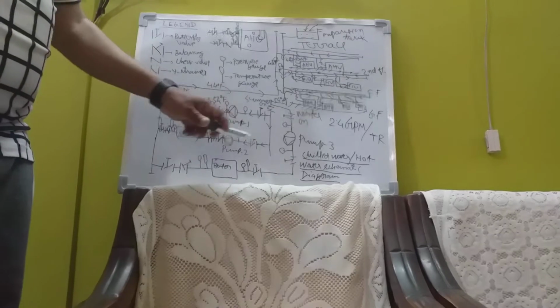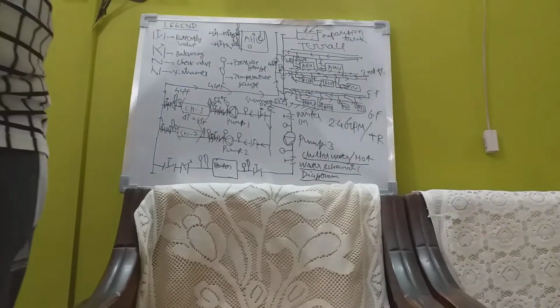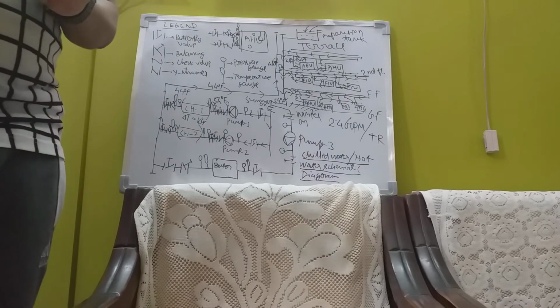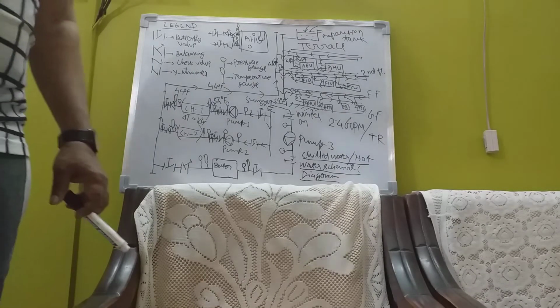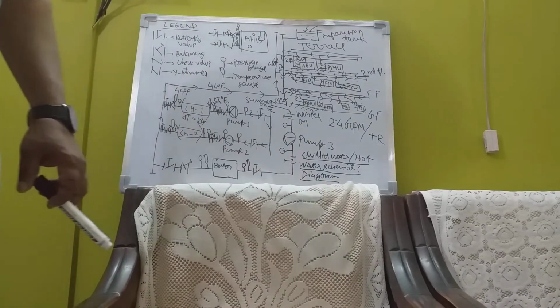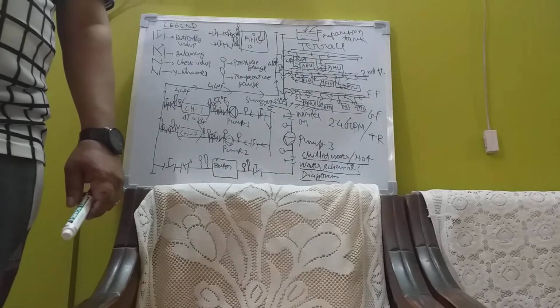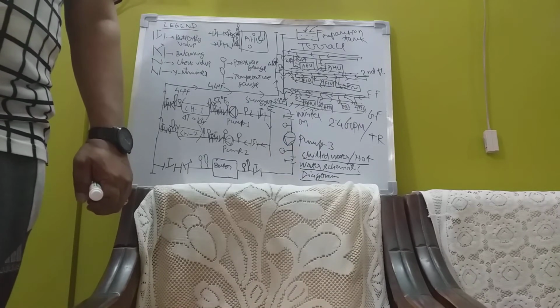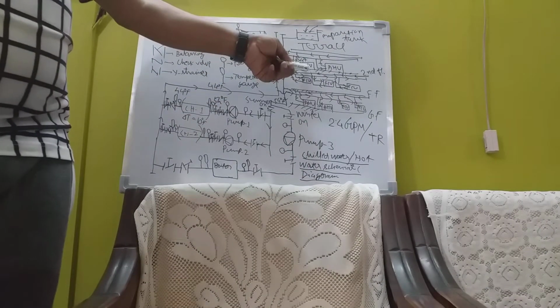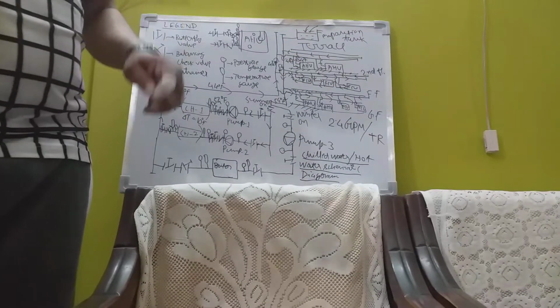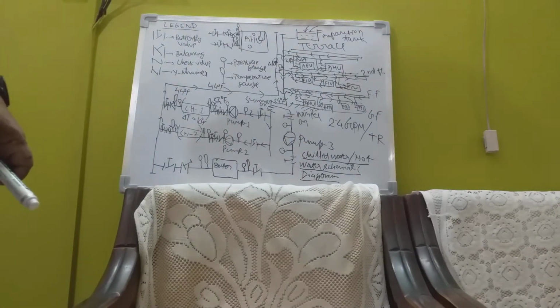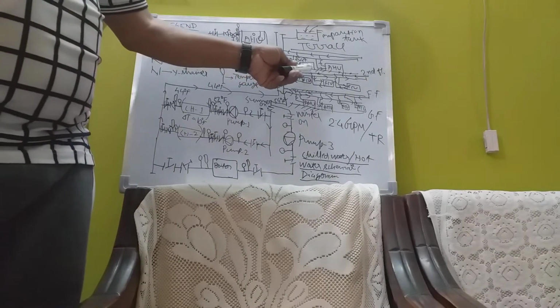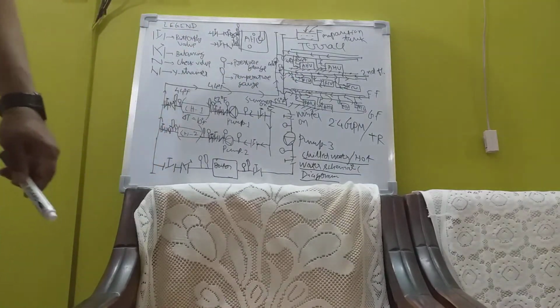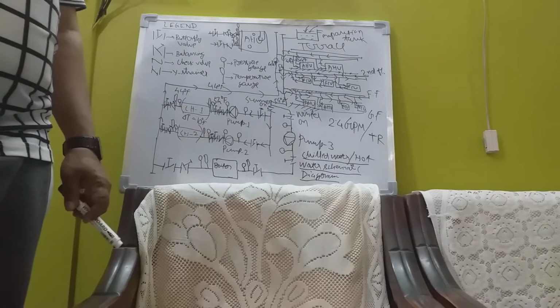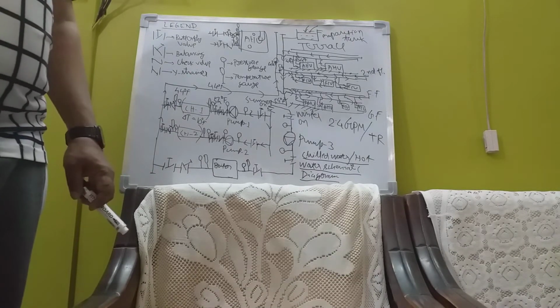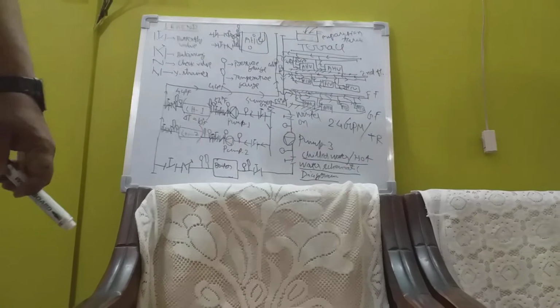Now, this is all about the chilled water system that I am talking about, the summer system, that is cooling. Now, there is another system, that is heating in winter. Other than cooling, there is heating in winter. The chilled water system will do the cooling in case of the AHU. In these same pipes, if I supply hot water in the winter season, the cold air through the AHU will pass over the hot water coil, get heated and be supplied to the system. System means the room. Hot air will be supplied to the room.